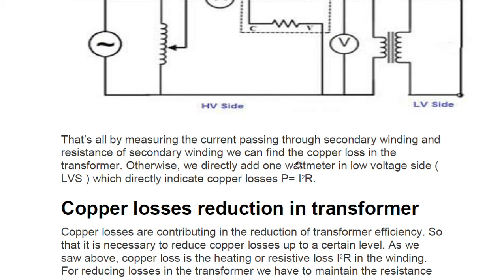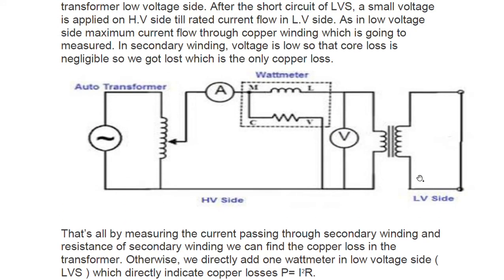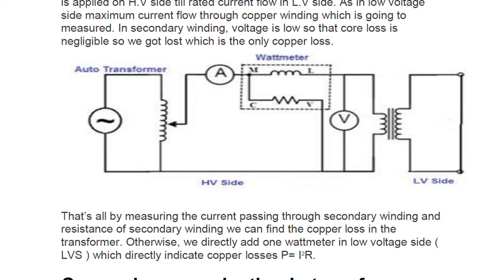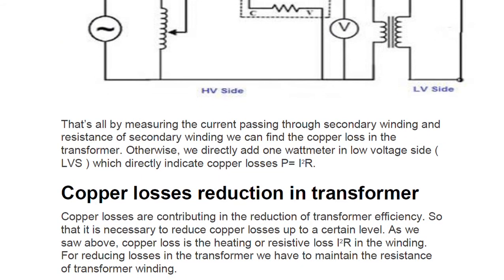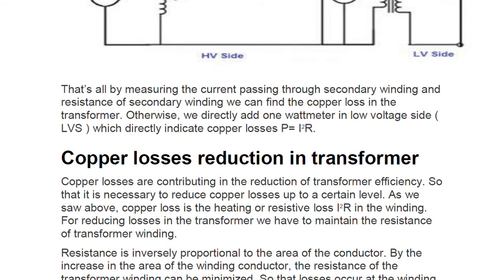By measuring the current passing through the secondary winding and the resistance of the secondary winding, we can find the copper loss. Alternatively, we directly add a watt meter on the low voltage side. The watt meter here directly indicates the copper loss, since P = I²R. Copper loss is proportional to the square of the current, so as you increase the load, copper loss increases.